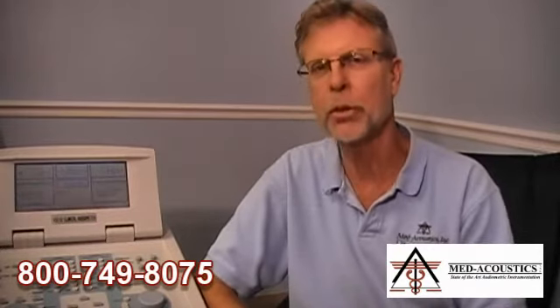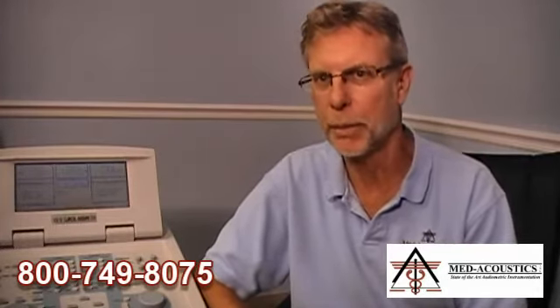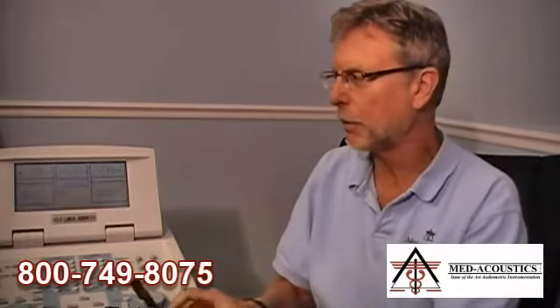You have to develop a system of doing it. Once you get used to it, you can do it in one minute. I would do it periodically — maybe once a week, say Monday morning, or at least once a month on the first clinic day. I wouldn't do it less than monthly. Some people do a listening check daily, which makes sense if you have older equipment that's more prone to problems. If you have a new booth and a new audiometer, once a month may be fine — and of course do it whenever there is any question.